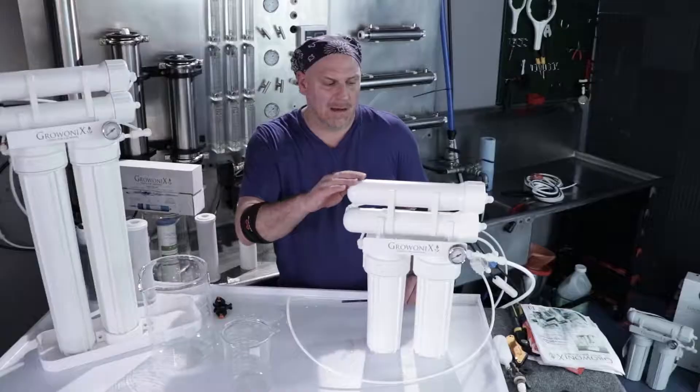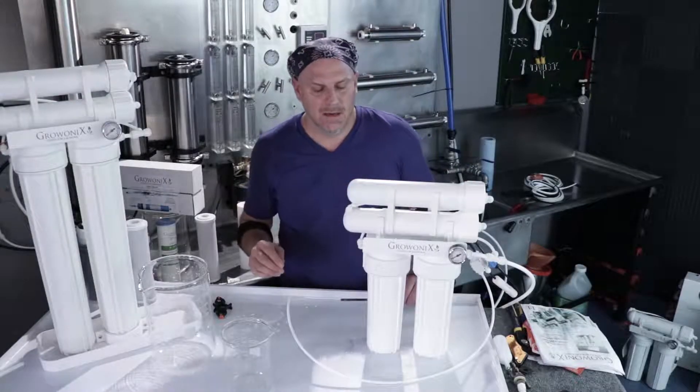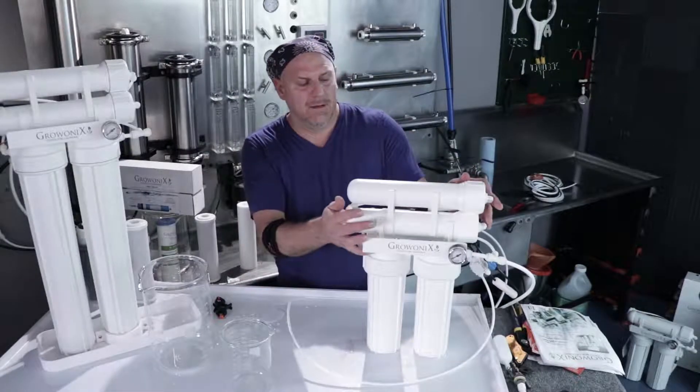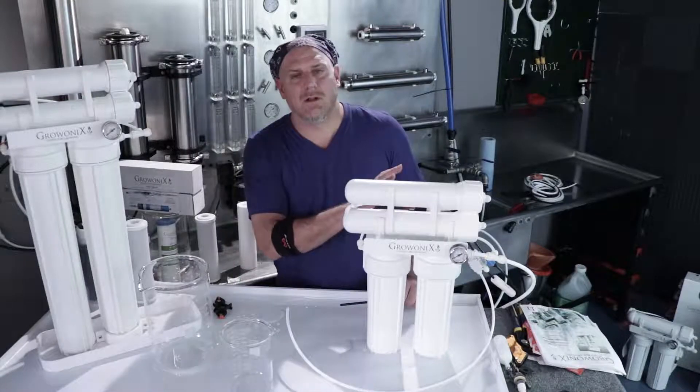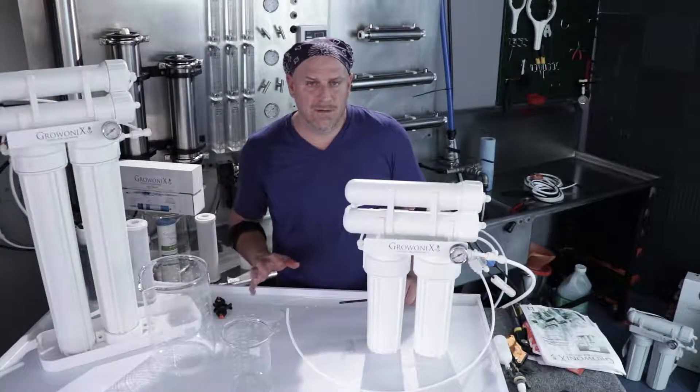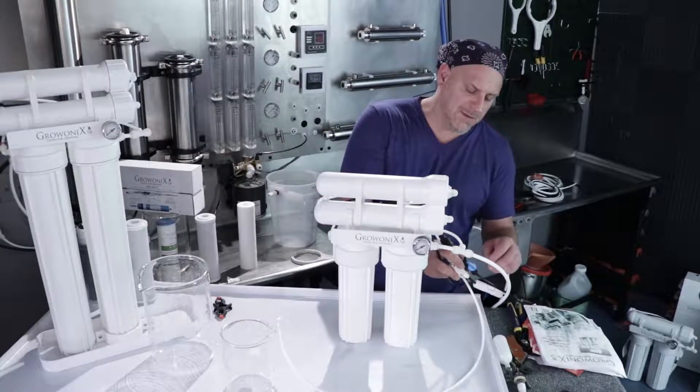Now we're going to flush the membrane. The membrane housing has not had water in it yet, so we've got to purge all the air out of it and flush the storage solution out of it. There's a glycerin-based storage solution in it, food grade, and we want to flush it all out before we use this water.